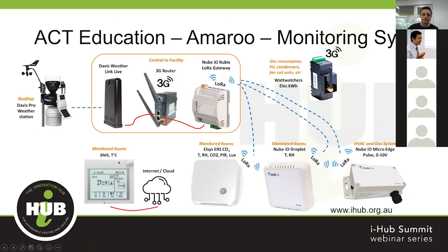What we are adding, down the bottom right, is the new Nube iO Micro Edge. This has a pulse counter and 3 zero-to-ten inputs. We're going to use this to capture the gas usage throughout their facilities, as well as the water—how much water is going through those heated slabs and what the temperature is going in and out of those loops. We also hope to capture whatever we can from their BMS system. All of that's in process right now.